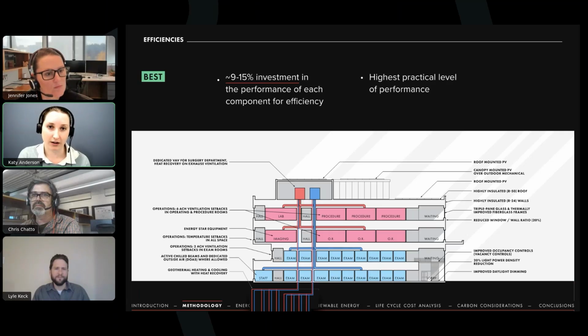This isn't allowed in all areas for outpatient healthcare, but in the areas where we are allowed to achieve those minimum air changes per hour set by regulatory requirements via active chilled beams, we've placed active chilled beams. So in exam rooms, for example, you're allowed to achieve the air changes via the induction from the active chilled beam, and so you can reduce the primary air coming from the air handler, which results in fan and conditioning savings.